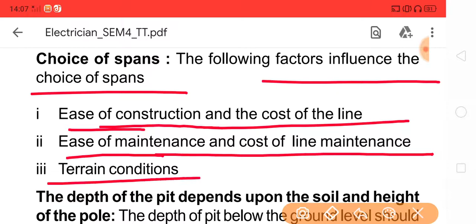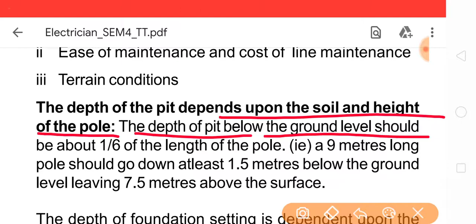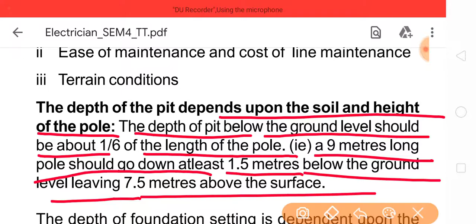Choice of span. The following factors influence the choice of span: construction cost of the line, maintenance cost of the line, and terrain condition. The depth of the pit depends upon the soil and height of the pole. The depth of the pit below the ground level should be about 1/6 of the length of the pole. A 9 meter long pole should go down at least 1.5 meters below the ground level, leaving 7.5 meters above the surface.